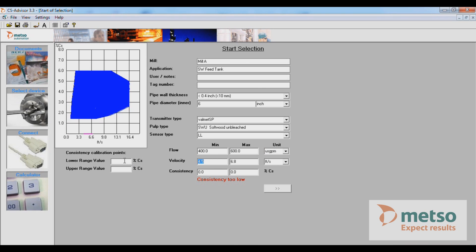And then we're going to go over here. Our 4 to 20 milliamp is going to range from 2 to 5, but our setpoint is 3% consistency. We're going to be controlling right around 3%. And these numbers here, the consistency around setpoint, is what determines the straight pipe requirements. So we want to get this as close as possible. When we put these numbers in, we look over here to the capabilities that are in the blue. This is the capabilities of the SmartPulp. The pink is our actual application and it's well within the blue area, well within the capabilities of this SmartPulp, this LL blade and for softwood unbleached in regard to the flows given and consistency given.